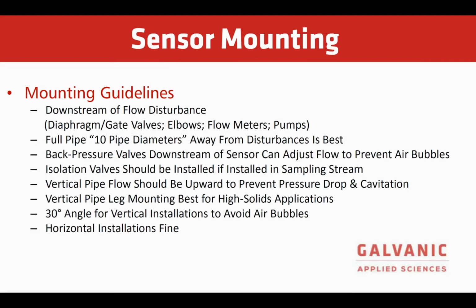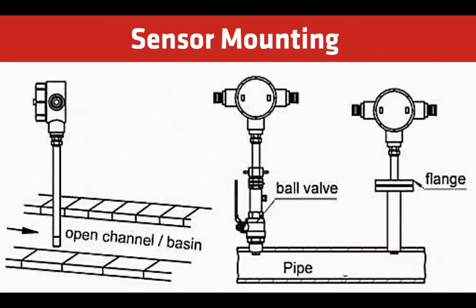Typically, they like to be mounted on a vertical pipe flow to prevent any pressure drop, and any air bubbles will not be able to stick in it. It will flow to the top. Again, vertical pipe is also best for high solids applications. Some horizontal applications are fine as long as the flow rate and the flow volume are enough to keep the piping full of liquid and without any air gaps in it, which would create air bubbles. Here are just some examples of different ways that these devices are used.